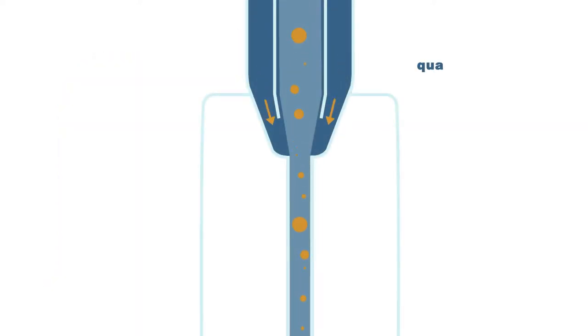The sample is transferred to a quartz cuvette. Due to the shape of the nozzle inside the quartz cuvette and the flow of sheath fluid, hydrodynamic focusing occurs. One event after the other moves like a string of pearls directly to the location of measurement. As the sheath fluid moves the events in the direction of the quartz cuvette, the movement is at laminar conditions and no turbulence is created.